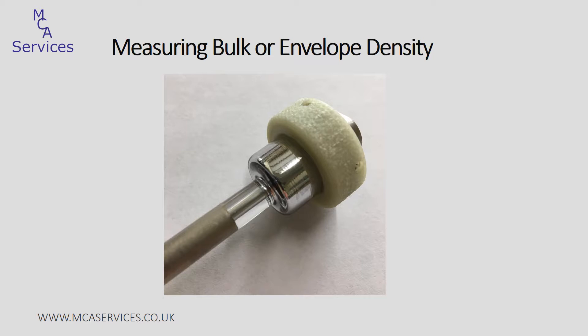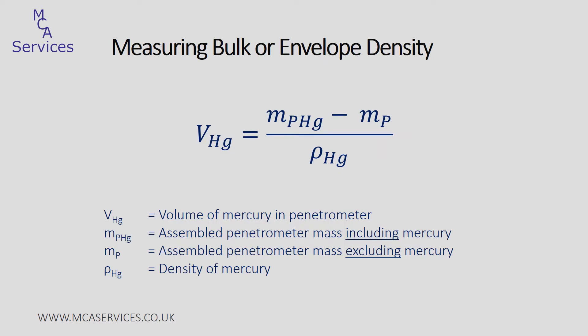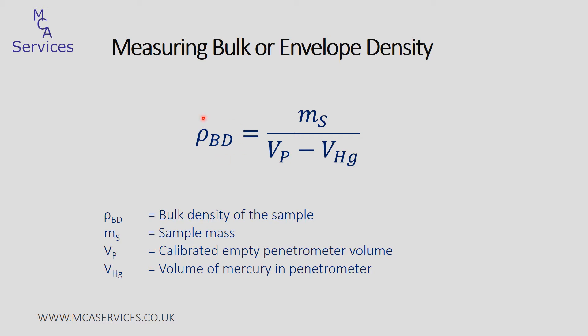We'll quickly run through the calculations that are applied — and bear in mind that all of this is shown within our mercury porosimetry videos. The first thing to be calculated is the volume of mercury within the penetrometer. To do that we subtract the mass of the assembled penetrometer without mercury from the mass of the assembled penetrometer with mercury — that's the mass before and after low pressure analysis — and that's divided by the density of mercury at the analysis temperature. We then calculate the bulk density by dividing the sample mass by the displacement volume of the sample. The displacement volume is calculated by subtracting the volume of mercury at the end of the low pressure analysis from the calibrated penetrometer volume. So essentially it's just sample mass over sample volume.